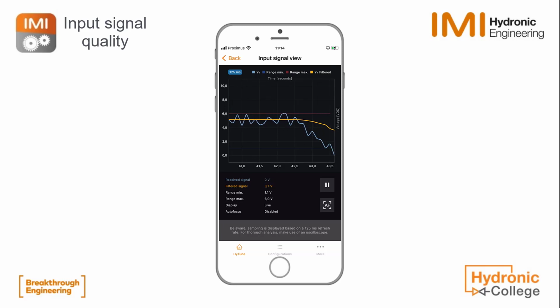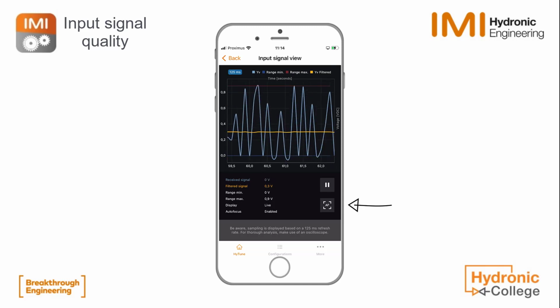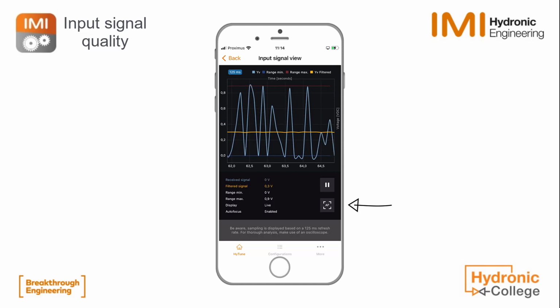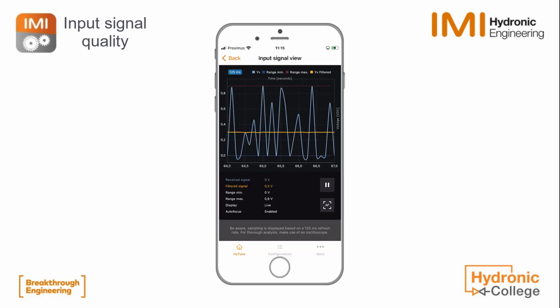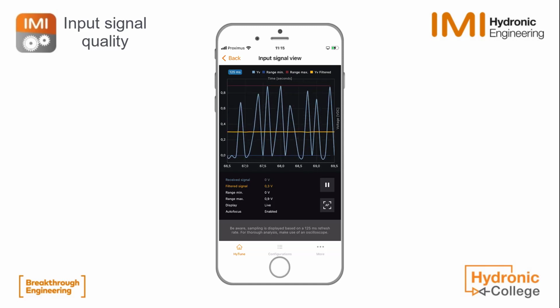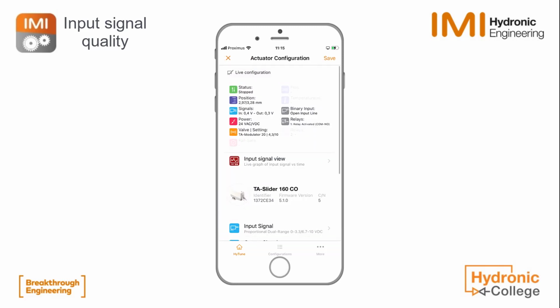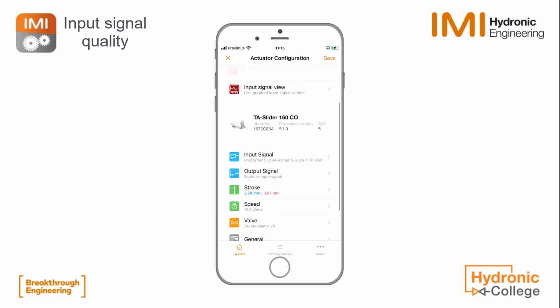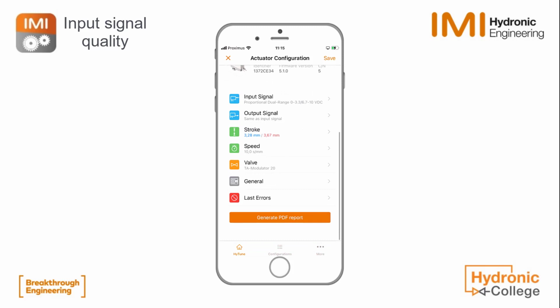Here now I am dropping the input signal, and you see we still have the same disturbances, and we see also that when our input signal should be 0, it's actually not. We have an average here of 0.3 volts, and this is the average value of the fluctuations. Again, when we click on focus, we see here what is happening. We see that we have 0.3 instead of 0 volt. Could cause the valve not to shut fully.